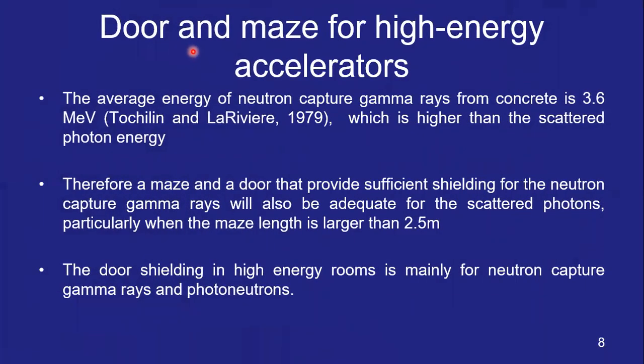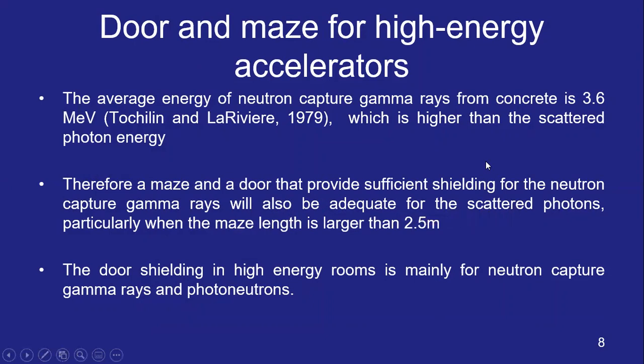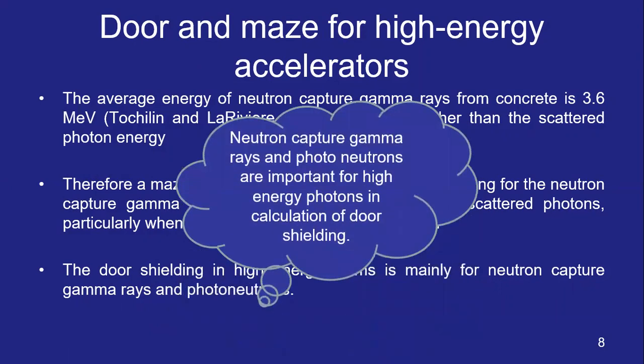Moving to door and maze design for high energy accelerators: the average energy of neutron capture gamma rays from concrete is 3.6 MeV, which is higher than scattered photon energy. A maze or door providing sufficient shielding for neutron capture gamma rays will also be adequate for scattered radiation, particularly when the maze length is larger than 2.5 meters. Door shielding in high energy rooms is mainly for neutron capture gamma rays and photoneutrons.